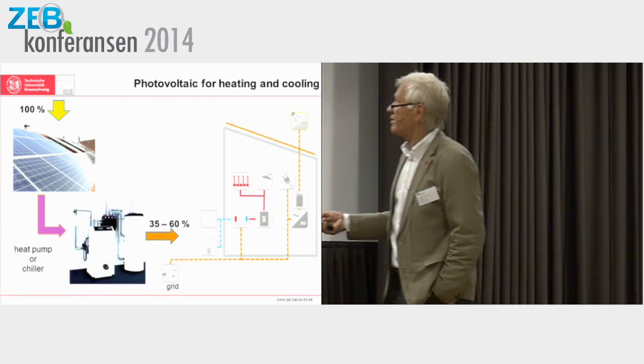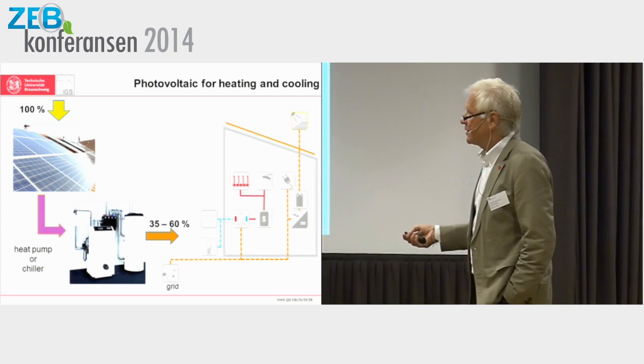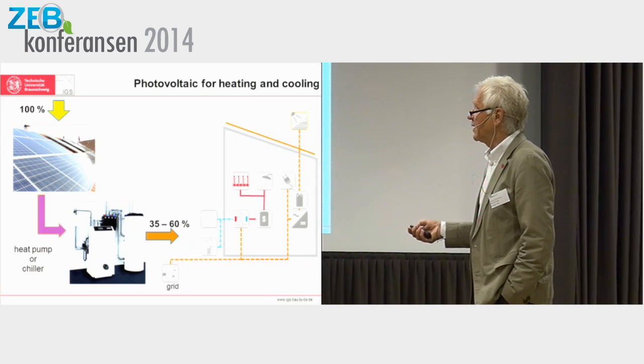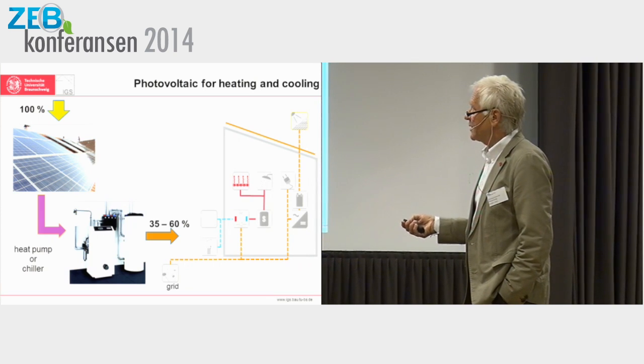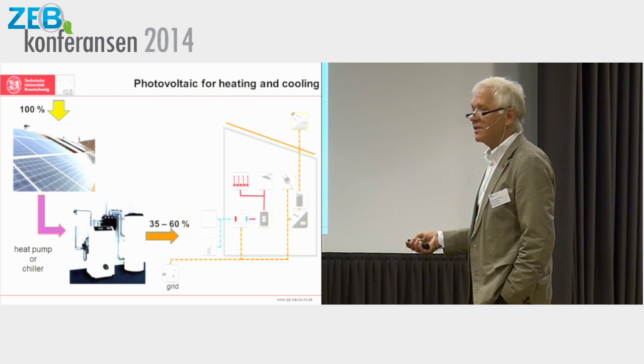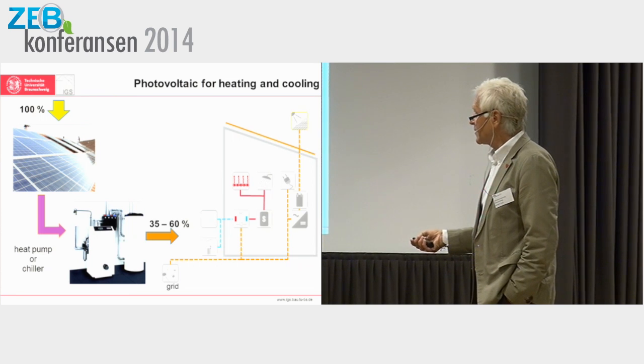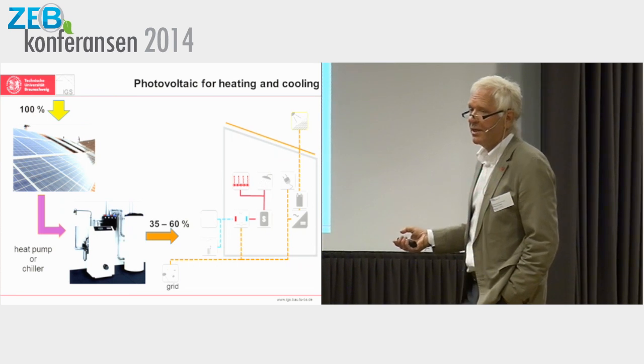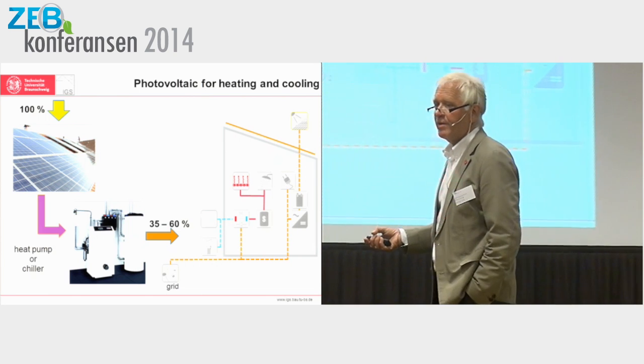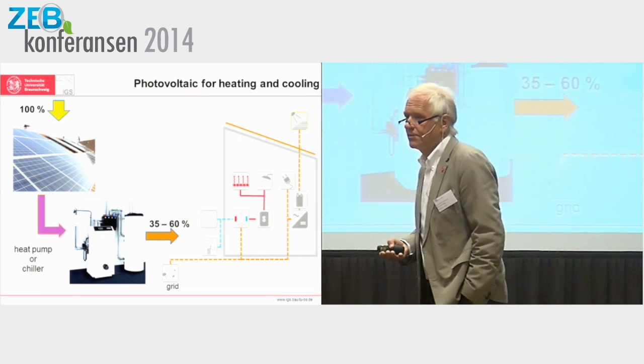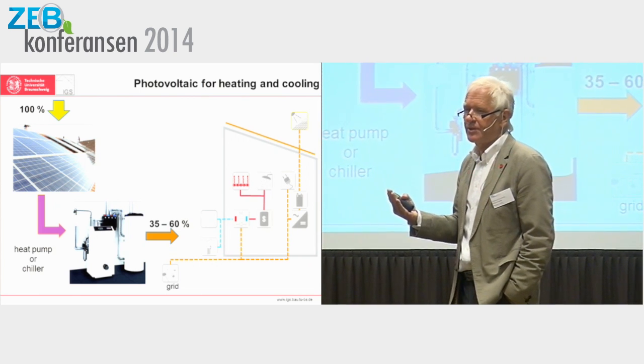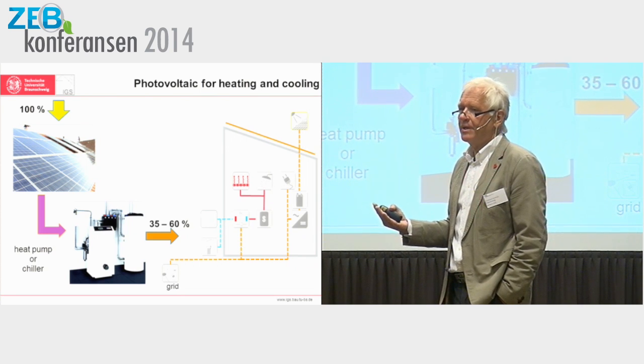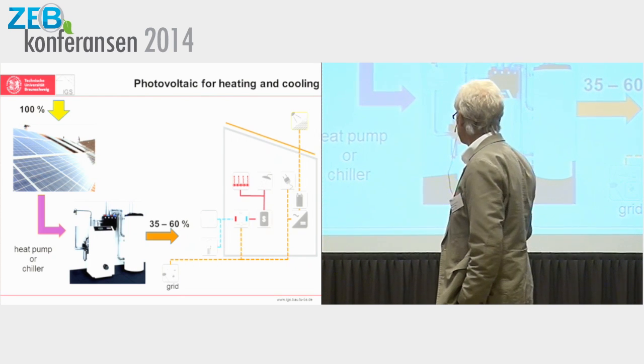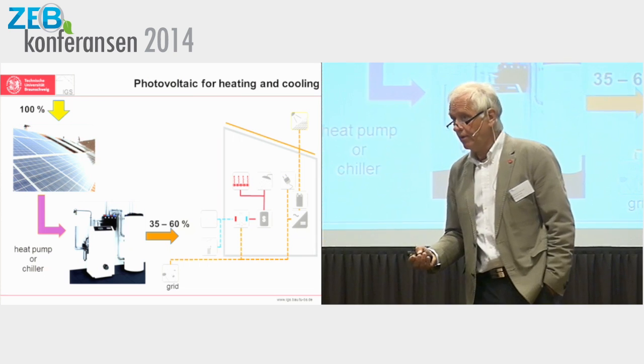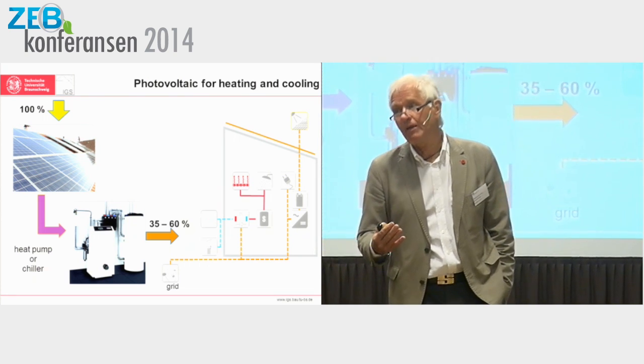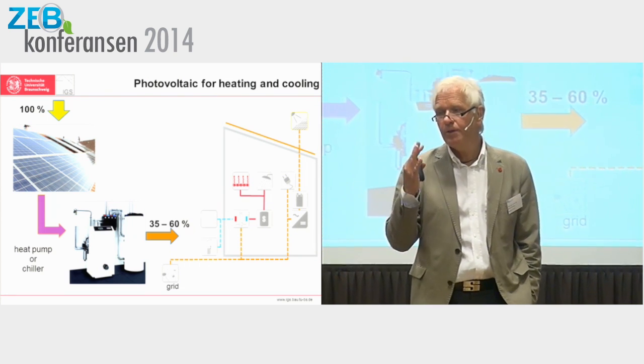Give you an example. Most people say PV has less efficiency, and this is right—from 100% solar, you only get 15% electricity. But with this 15% electricity and a good heat pump, you make 60% energy, because the heat pump has a COP of 4. This means 4 multiplied by 15% is 60%. So finally, the energy that comes out of this system is 60%, and the solar thermal system has to fight for that 60% over the year.